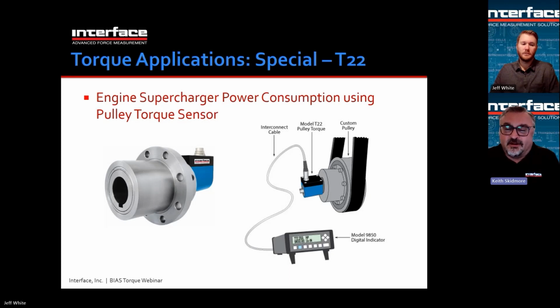And then the blue part is really just an assembly that allows the rotating electronics for the signal and power transfer. So the entire shiny part spins along with the motor shaft, and there's a pulley attached to that. You can see in the picture on the right, there's a belt, and that belt tension is reacted by the motor shaft, not the torque sensor bearings. And so the torque sensor housing is just along for the ride. Think of it as a slip ring assembly. It's induction, but it's the same idea. And then you get torque and speed, conventional power. This shows our model 9850 digital display for that. Moving on.